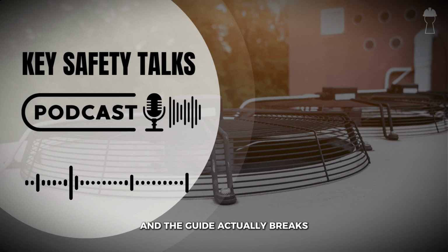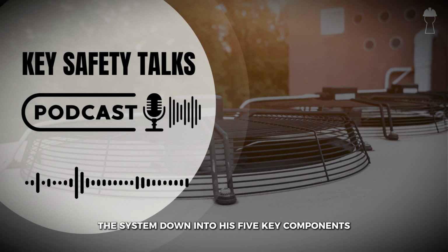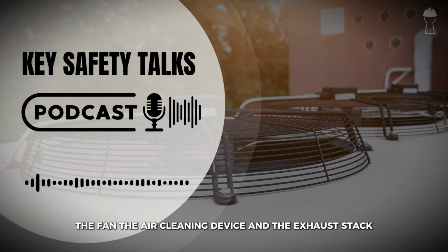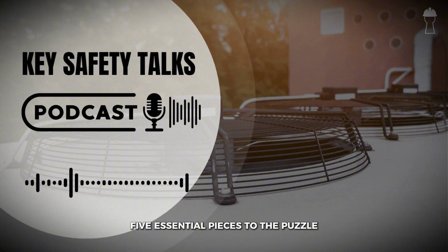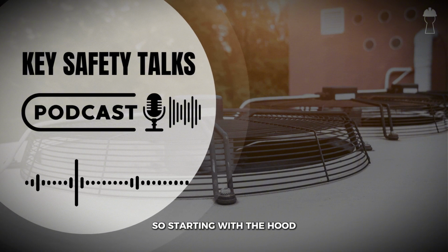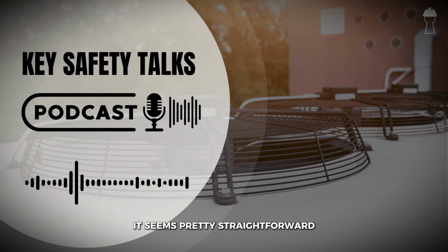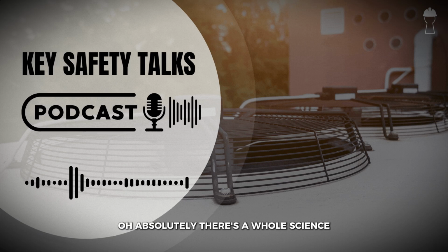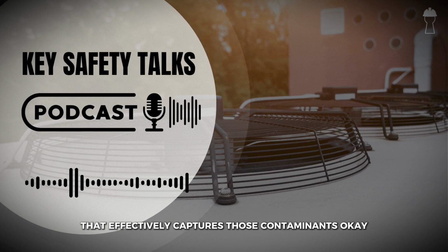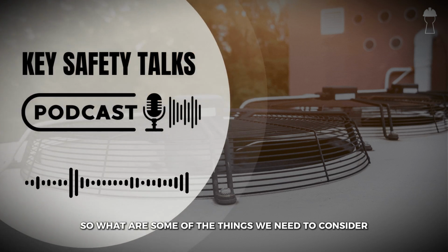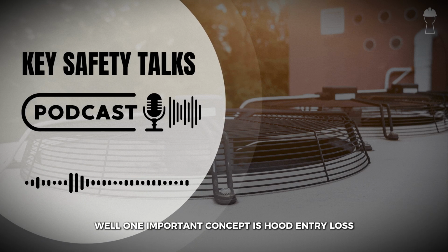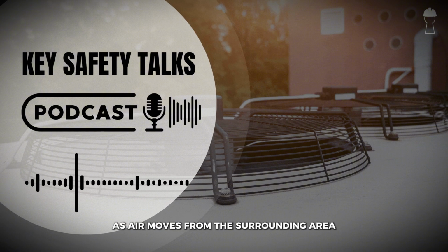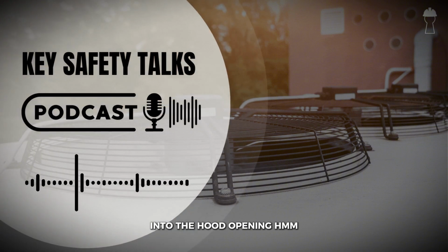And the guide actually breaks this system down into its 5 key components: the hood, the duct, the fan, the air cleaning device, and the exhaust stack. 5 essential pieces to the puzzle. So starting with the hood, it seems pretty straightforward, but there's actually a lot more to it than meets the eye, right? Oh, absolutely. There's a whole science to designing a hood that effectively captures those contaminants. Okay, so what are some of the things we need to consider? Well, one important concept is hood entry loss. Basically, it's the energy that's lost as air moves from the surrounding area into the hood opening.